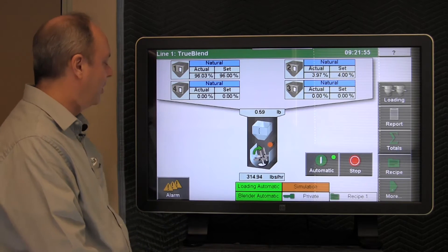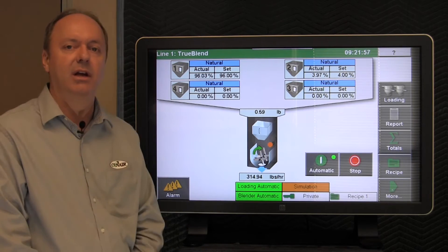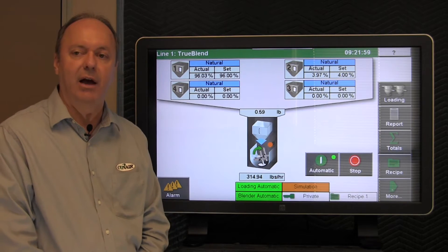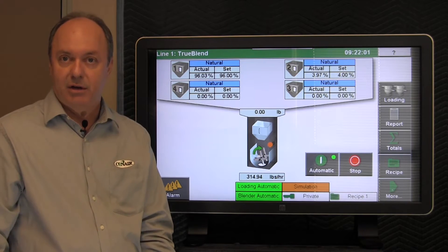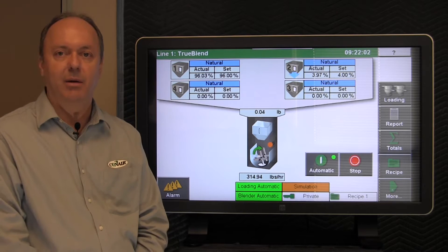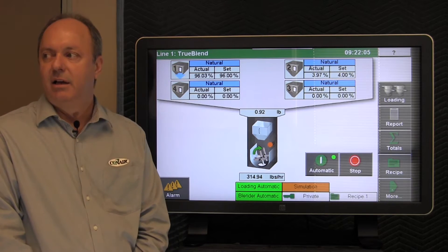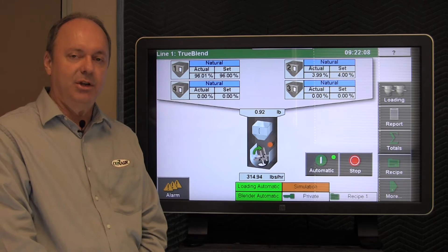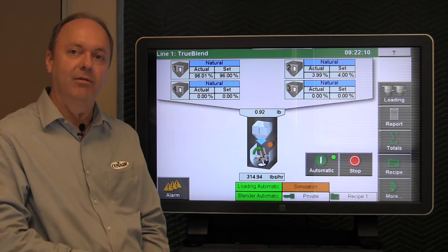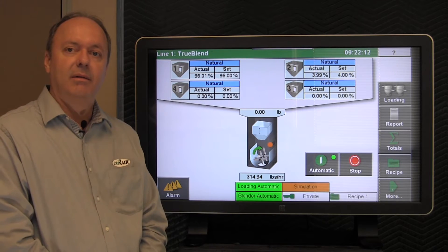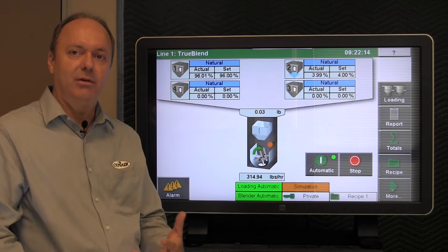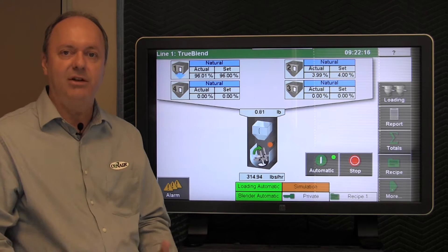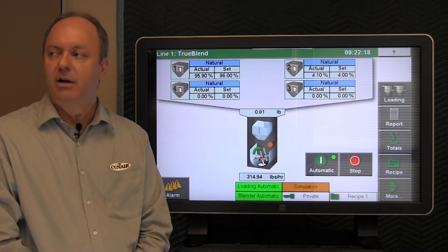In addition to that, you would also get an alarm indication that would indicate that the blender is either running out of spec. It would tell you the component hopper that's out of spec. It would say component one is out of spec. You may have an alarm that indicates the material flow is not repeatable from batch to batch. The material is flowing irregularly from batch to batch, so you would get a material flow error.